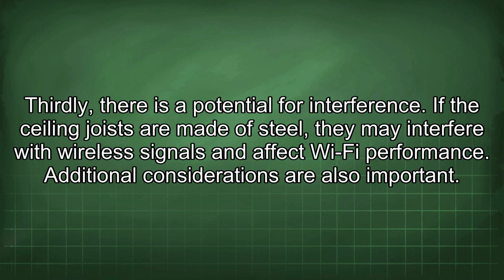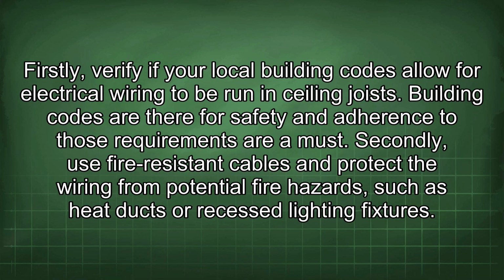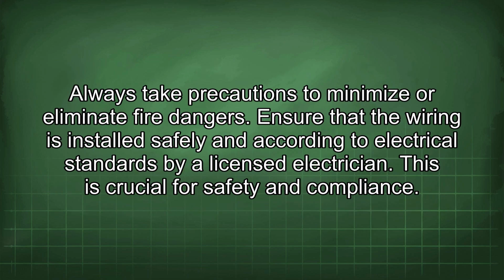Additional considerations are also important. Firstly, verify if your local building codes allow for electrical wiring to be run in ceiling joists. Building codes are there for safety, and adherence to those requirements is a must. Secondly, use fire-resistant cables and protect the wiring from potential fire hazards, such as heat ducts or recessed lighting fixtures. Always take precautions to minimize or eliminate fire dangers. Ensure that the wiring is installed safely and according to electrical standards by a licensed electrician. This is crucial for safety and compliance.